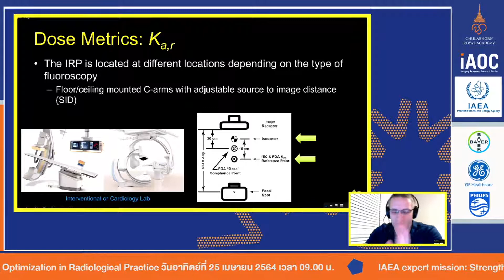All right, so here I just give a simple list. Every system, every vendor, every configuration out there will have to define its interventional reference point. It's always defined the same place, but every system will have a subtle difference just because of the geometry, the size of the machine. And so you need to know exactly where your interventional reference point is so that you can do some dose calculations, which I'll show in a moment.